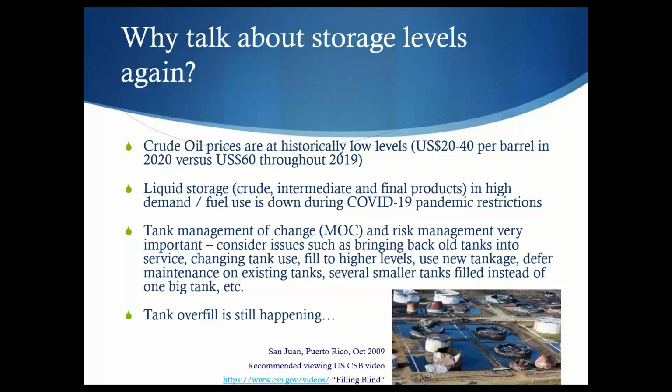So tank overfill is still happening. Four years after Buncefield, there was another incident, and it was called Capeco. Capeco was an oil storage facility in the Caribbean, and they had a fairly large overflow, and you can see the photo at the bottom here, in Puerto Rico, October 2009. Now, if anyone hasn't heard about this one, it was very similar to Buncefield that happened four years before in the UK. One of the tanks overflowed, causing a fire and explosion, and as you can see, devastation to all the other tanks in the tank farm nearby.